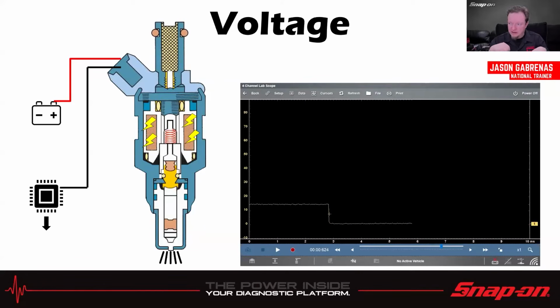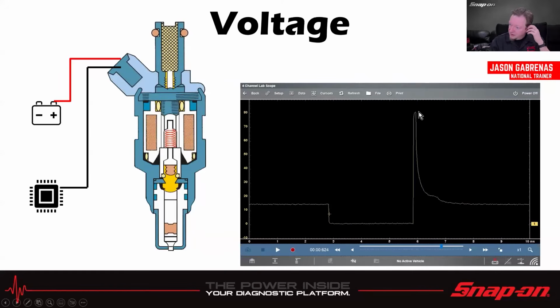So it gets induced back into the line. That's why we get the kick at the end. That's when it releases. And then this little bump right here is actually the point where that pintle snaps shut back on the seat. You get a little extra kick right there too. Then it goes back to baseline, and when it opens again, it does it again.